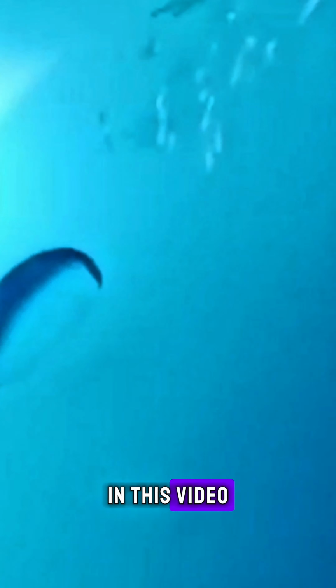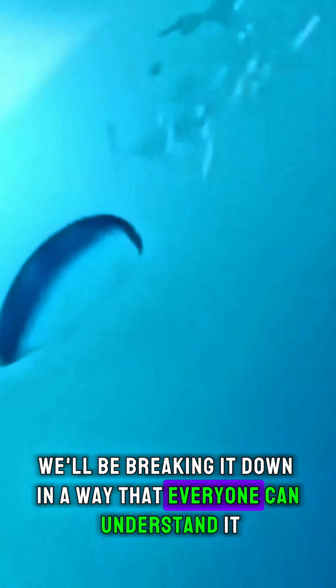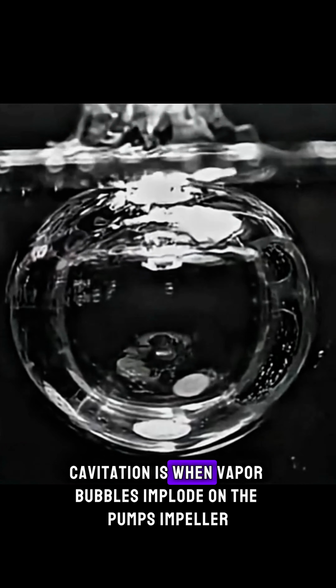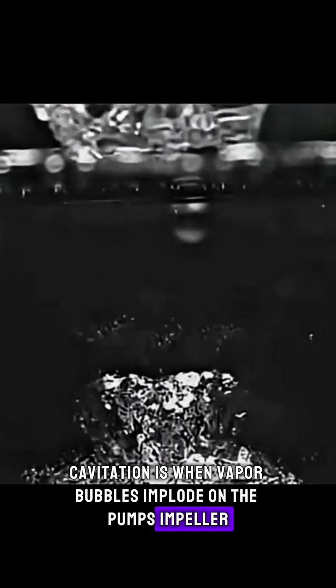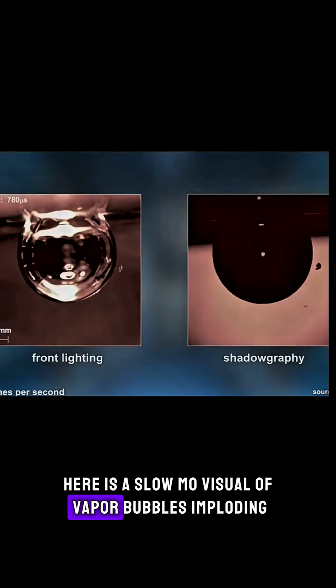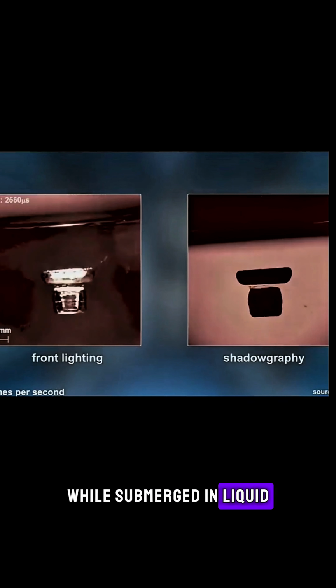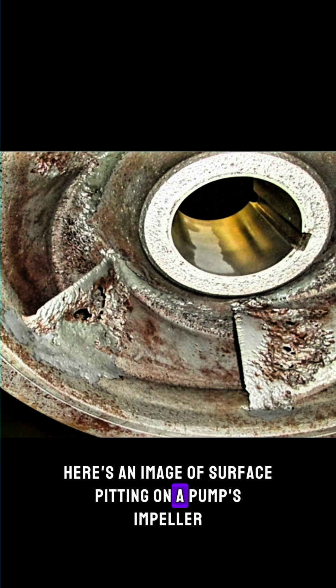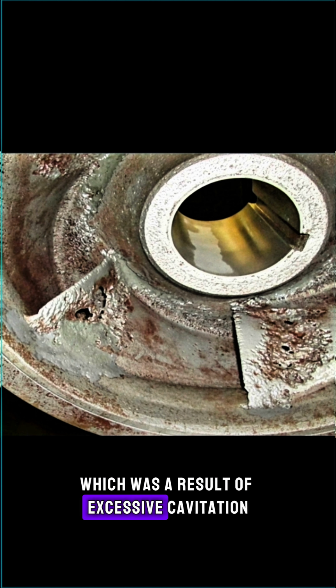Let's talk about centrifugal pump cavitation. In this video, we'll be breaking it down in a way that everyone can understand it. Cavitation is when vapor bubbles implode on the pump's impeller. Here's a slow-mo visual of vapor bubbles imploding while submerged in liquid. Here's an image of surface pitting on a pump's impeller, which was a result of excessive cavitation.